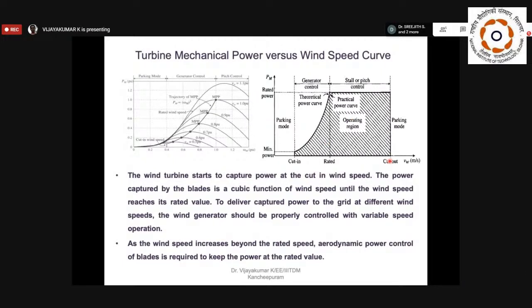Here I want to convey three regions. One is cut-in speed. Cut-in speed is the speed at which they can start the wind turbine to generate power. Below cut-in speed, they won't allow the generator to rotate. The reason is that the losses are more below cut-in speed. The losses themselves are enough to compensate the generated power, so there is no use in operating the machine below cut-in speed. After cut-in speed, they allow the machine to operate till rated speed.